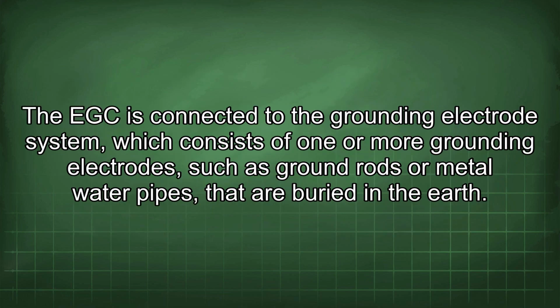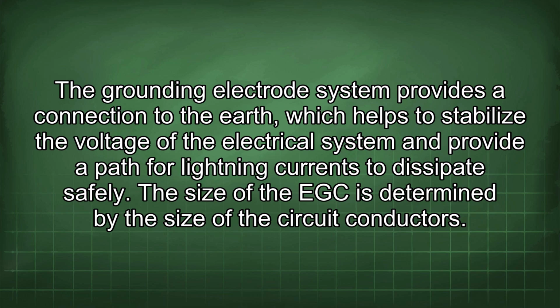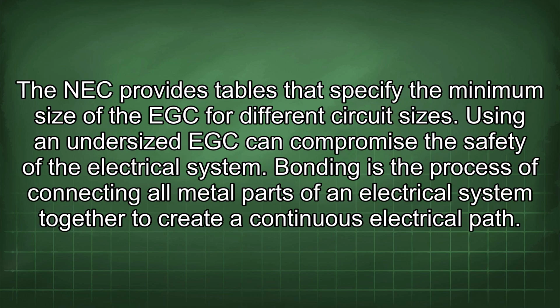The EGC is connected to the grounding electrode system, which consists of one or more grounding electrodes, such as ground rods or metal water pipes, that are buried in the earth. The grounding electrode system provides a connection to the earth, which helps to stabilize the voltage of the electrical system and provide a path for lightning currents to dissipate safely. The size of the EGC is determined by the size of the circuit conductors. The NEC provides tables that specify the minimum size of the EGC for different circuit sizes. Using an undersized EGC can compromise the safety of the electrical system.